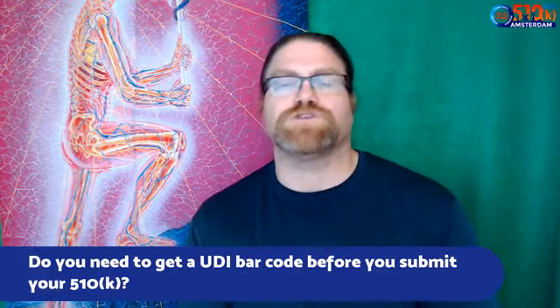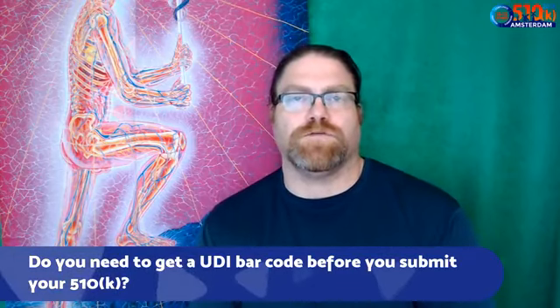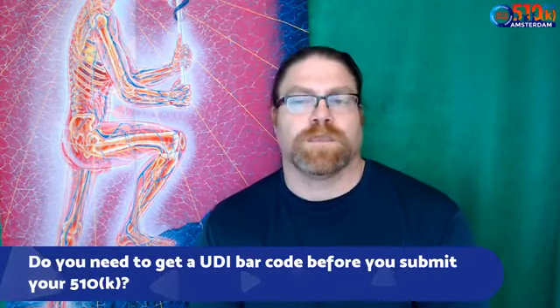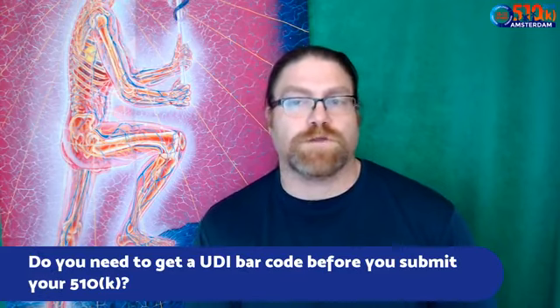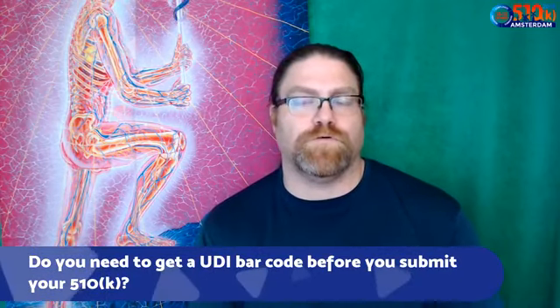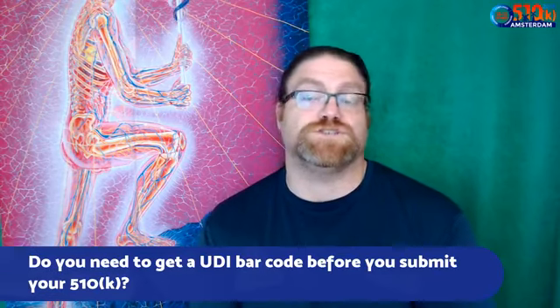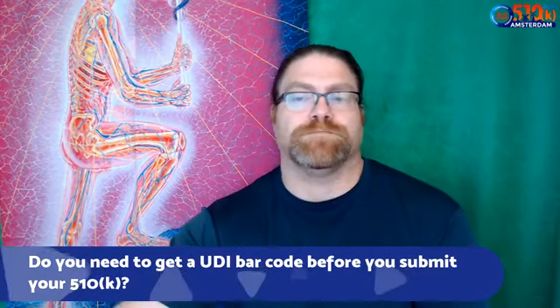And it's only when you actually put the product in the market and start distributing it that you need the UDI codes. You can also do it before you do all that, because the FDA doesn't approve you getting a UDI barcode. You work through a separate third-party agency, such as GS1, to get your barcodes.